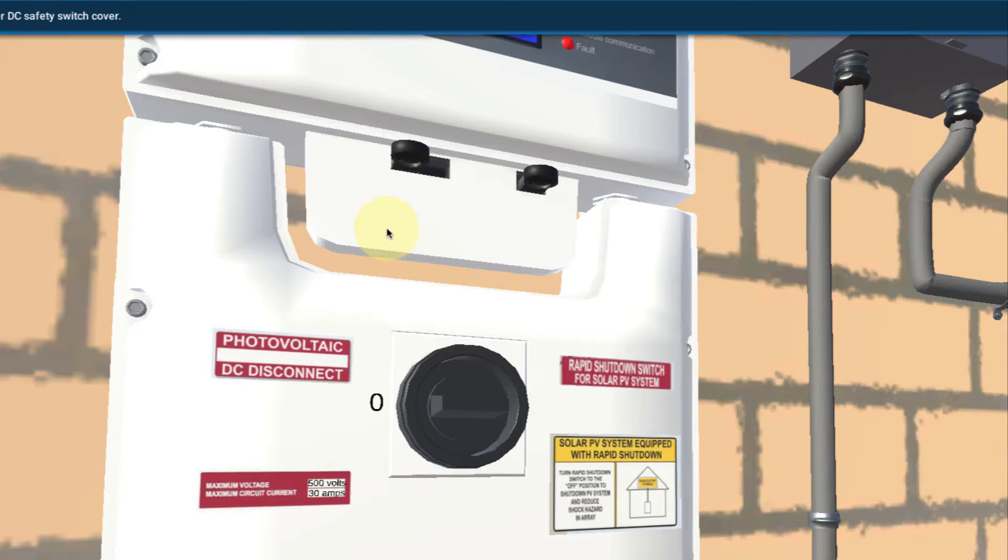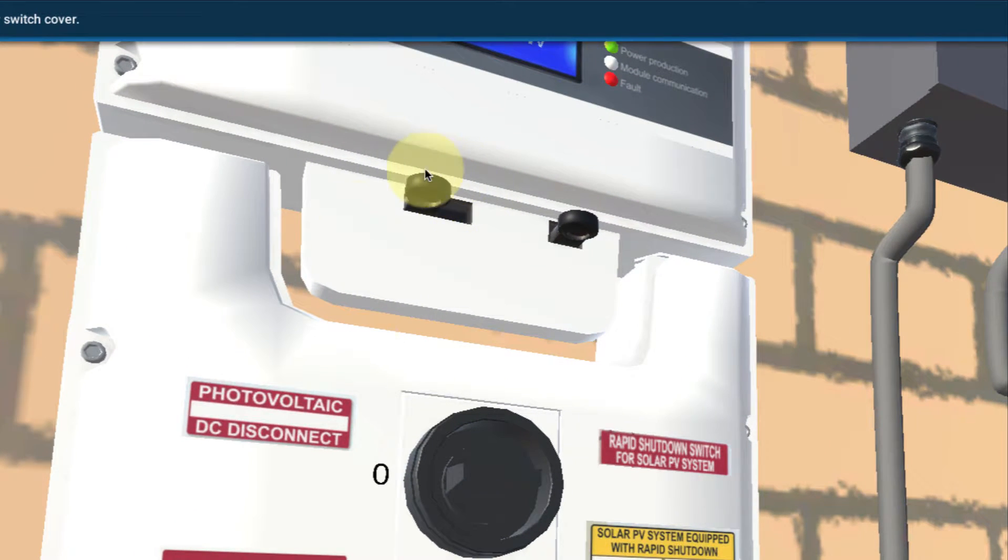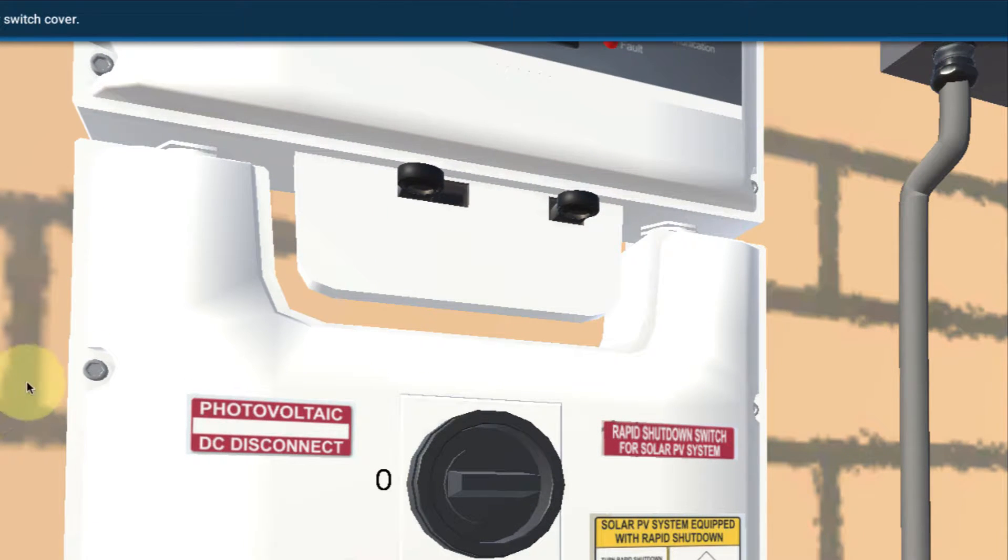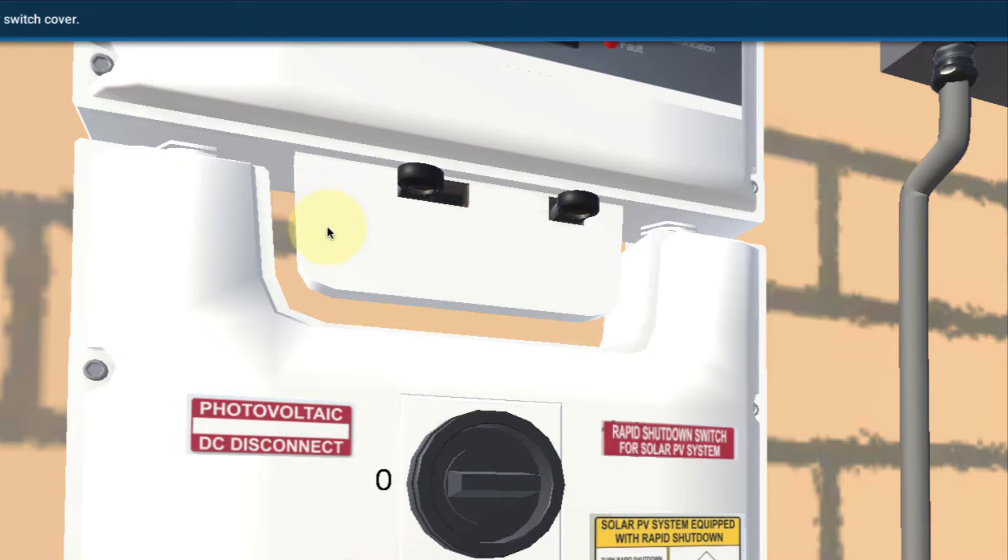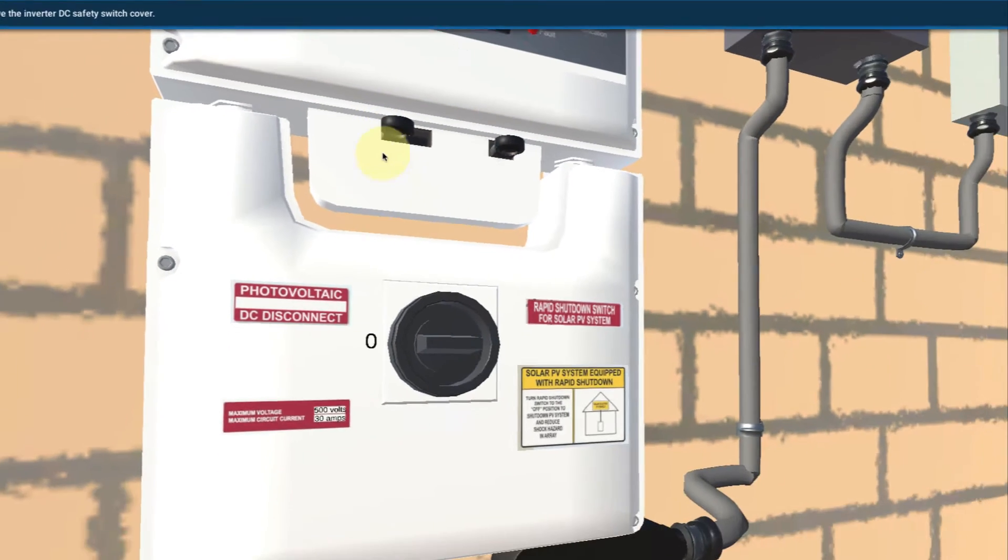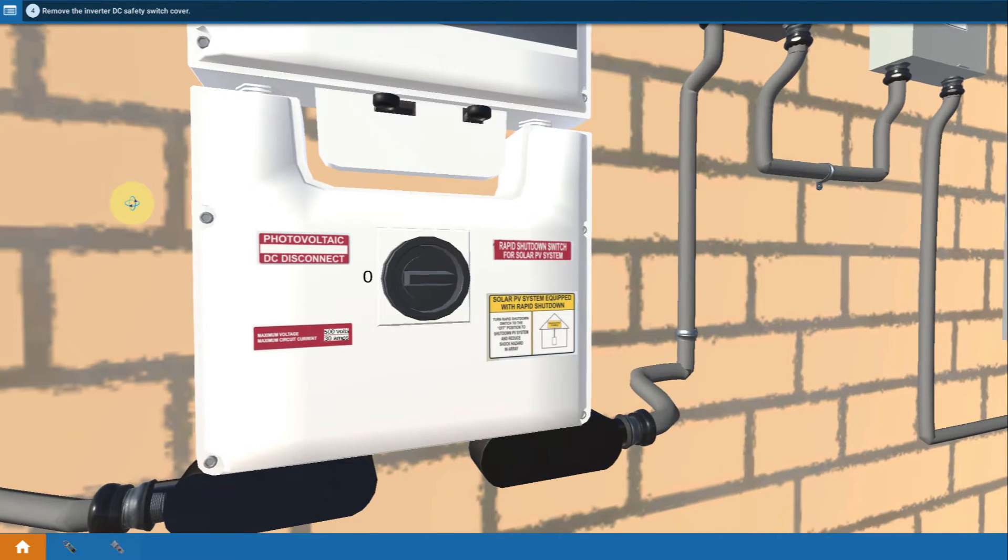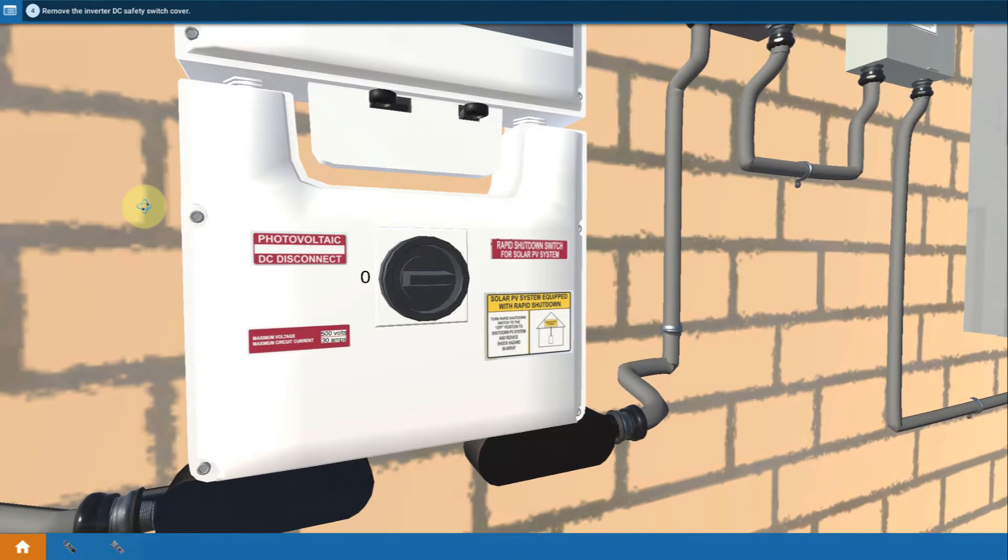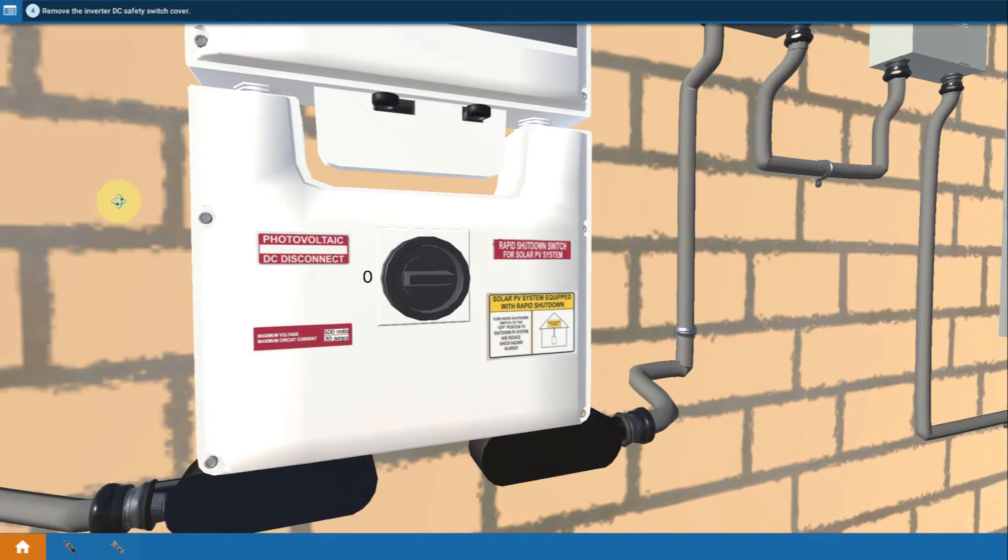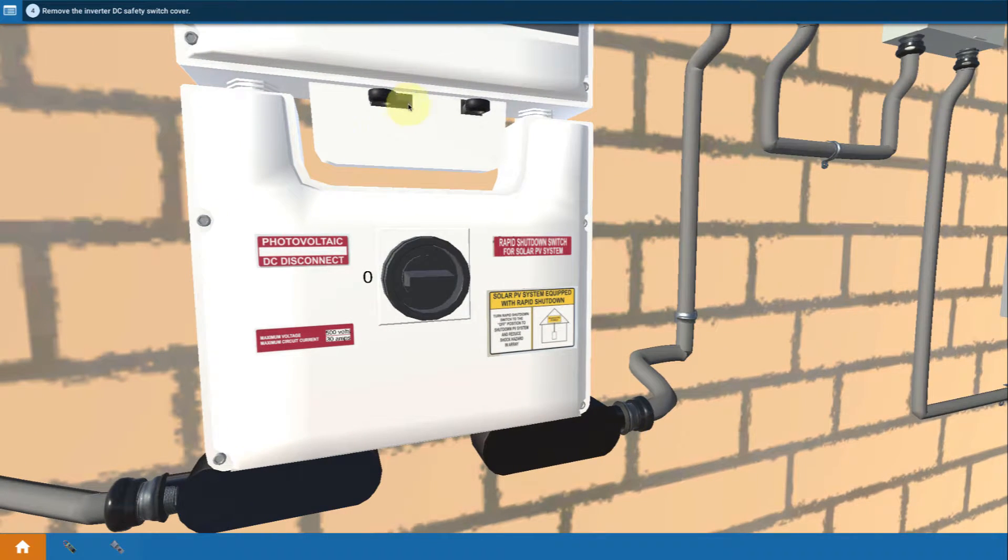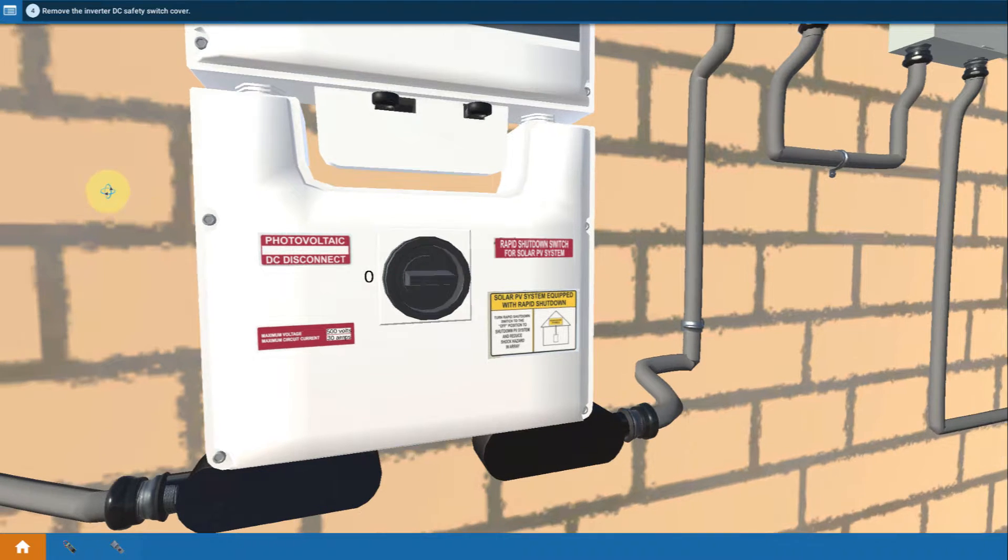This switch up here is the switch that actually tells the optimizers to turn on. So you can be connected to the array, but you have not sent what's often called a heartbeat signal up to the optimizers to say, hey, come out of your safe mode and start actually optimizing and outputting power. So there's these two switches, and they'll be used in electrical commissioning and troubleshooting and so on. But just wanted you to know that in the case of an optimizer system, there's more than just one switch. There's actually another switch that turns on the optimizers and tells them to operate.